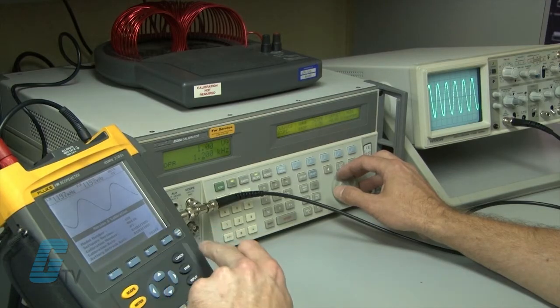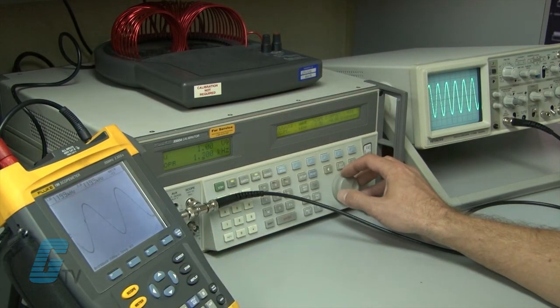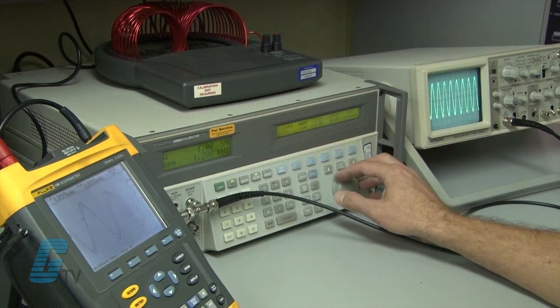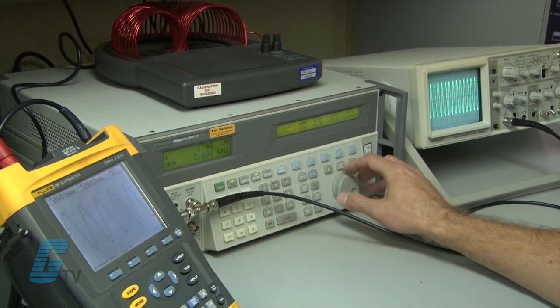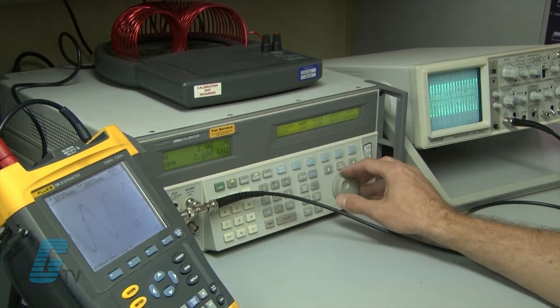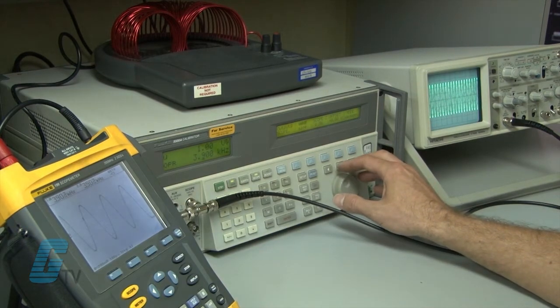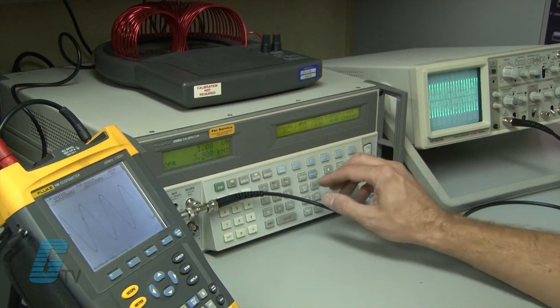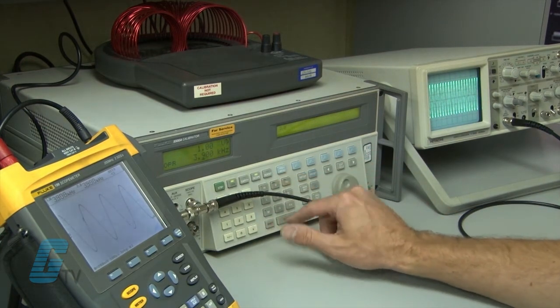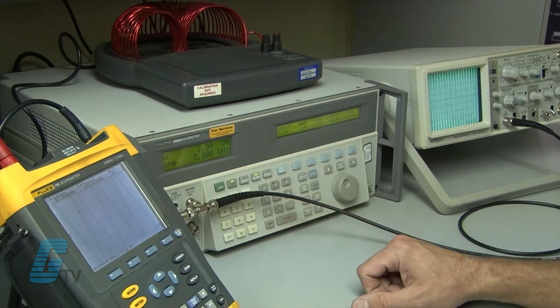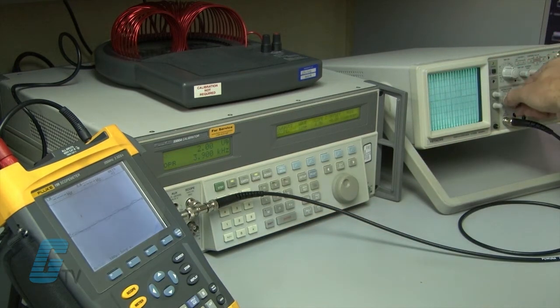It is important to remember to periodically run calibrations on equipment both old and new. A common misunderstanding is that new instruments do not require any calibration. It is not guaranteed that every new piece of equipment will perform exactly within its desired specifications. Calibrating the instrument prior to installation can potentially save you time and money.